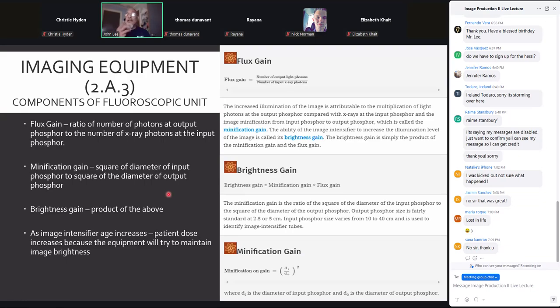Now, there are three formulas that you need to be familiar with when talking about the image intensifier. I want to go to the brightness gain first. The brightness gain tells us how well the image intensifier takes the X-ray information and converts it to visible light. We figure that out by multiplying the flux gain times the minification gain. All right, brightness gain is the product of flux and minification. Very simple.